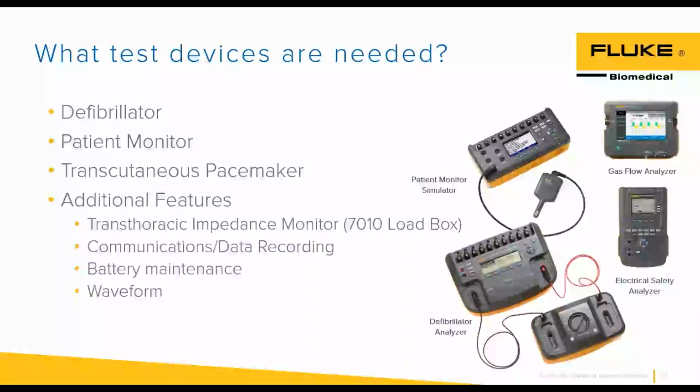So we're going to need something that can test the functionality of this device. On the right side of the screen, we have just Fluke Biomedical solutions. They're not the only solution, but these are the solutions that we have for testing defibrillators.